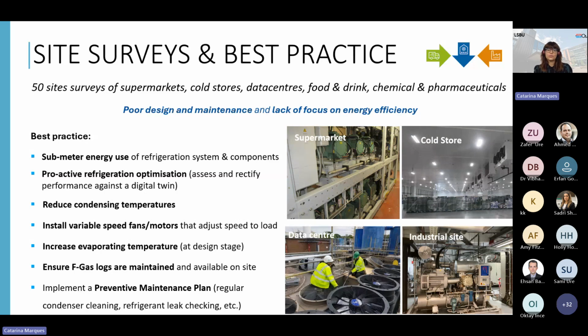We also found a lot of high condensing temperatures - this is a picture of a blocked condenser, and we found these all the way from supermarkets to data centers. So there's a lot that can be done with improved maintenance, such as opportunities to install variable speed fans and motors that adjust speed to the load.